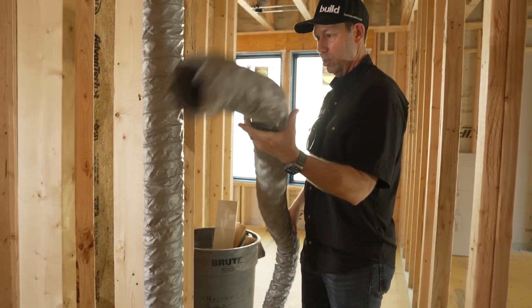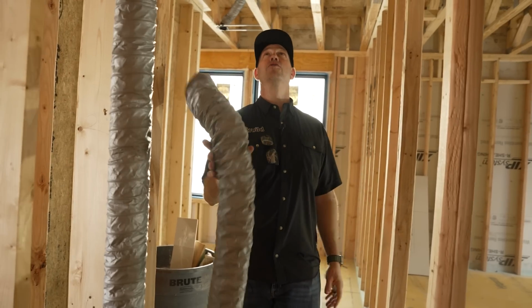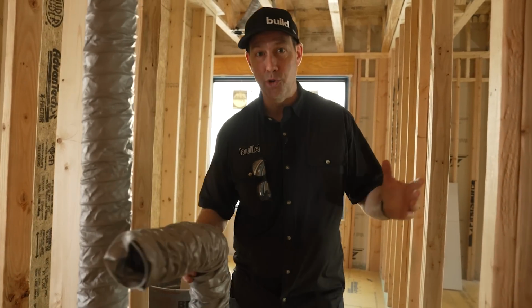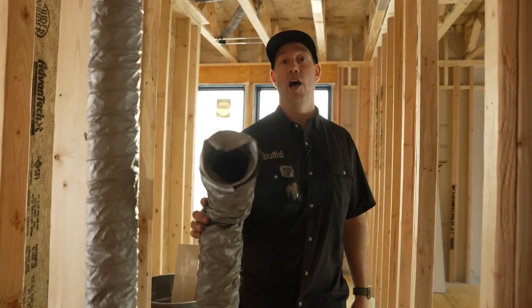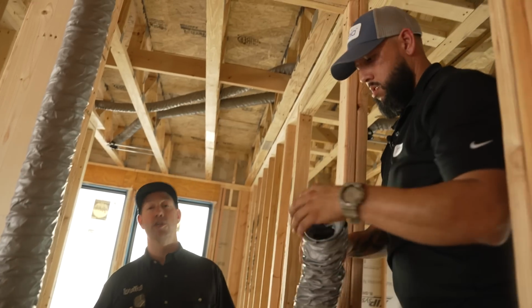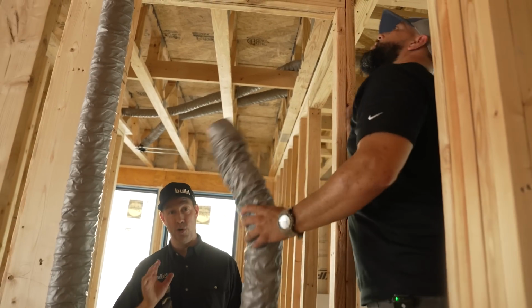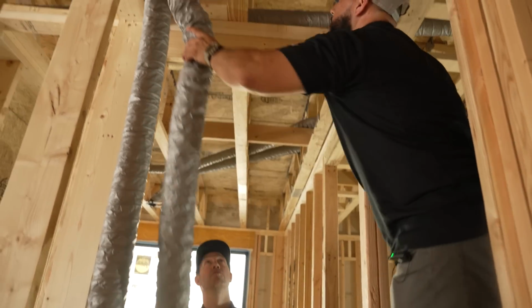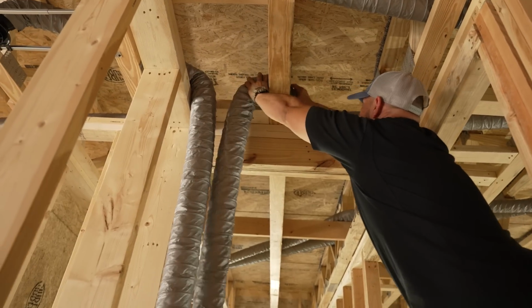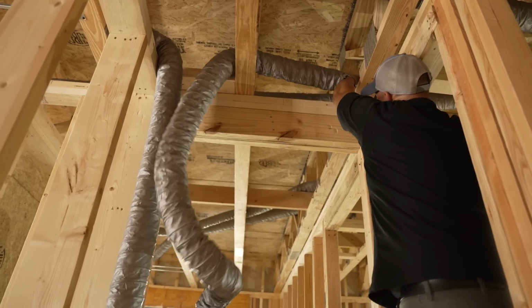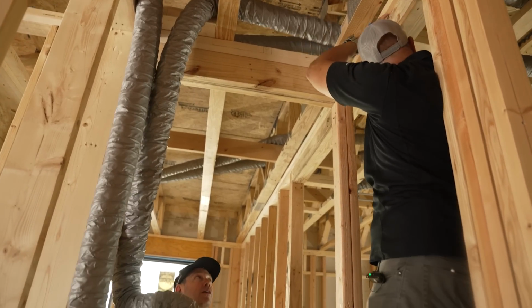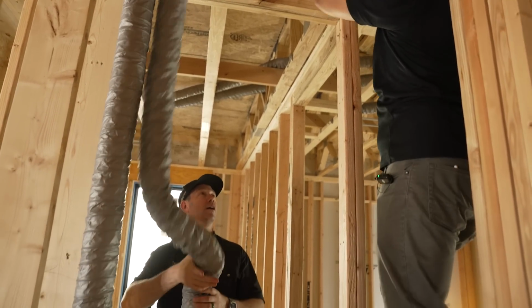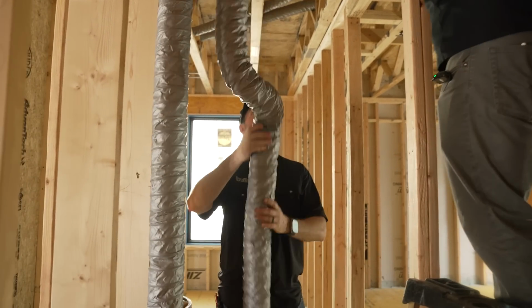And remember, the model called for 38 feet. But if we run into problems and we do 40 feet or even 45 feet, it's no big deal, because we can commission this at the end and we're putting that flow hood on. At the very end of this, we'll go ahead and commission this. We'll measure that airflow, and that damper will be adjusted per the software to tell us where it needs to be to meet the design of this home.